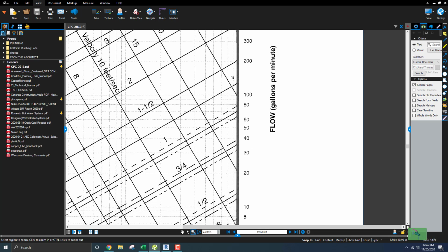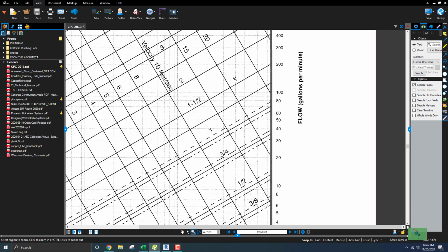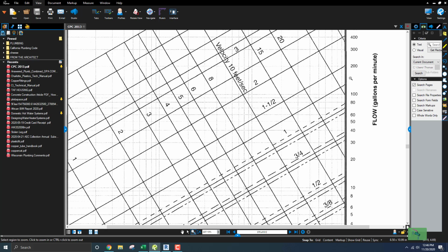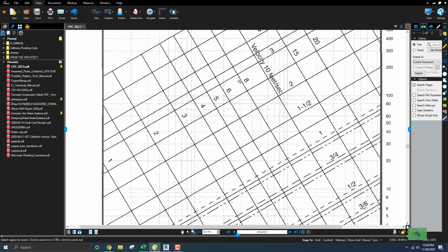Looking at that, we can go up to 110 GPM. So it's about here, right? And for cold water, I think we can use no more than 8 velocity. So it's about right in here, 2.5. Now let's go over some more. 110, it's about in here, I would say. So it could be between 2.5 and 3 inches of pipe, to be on the conservative side.